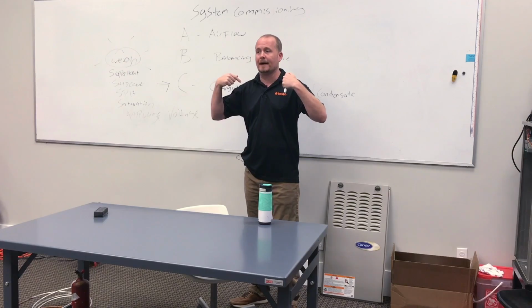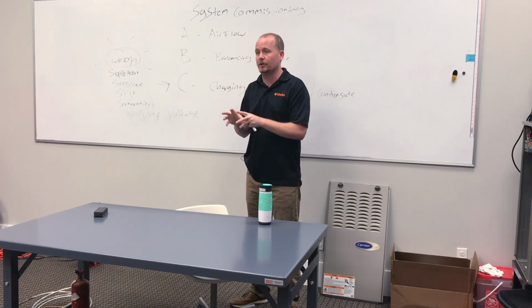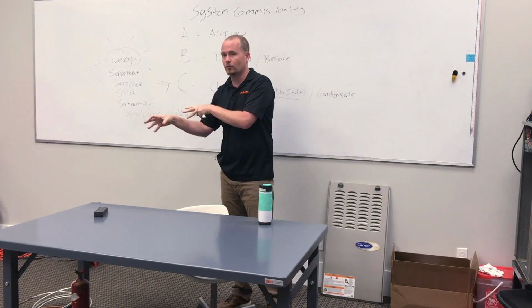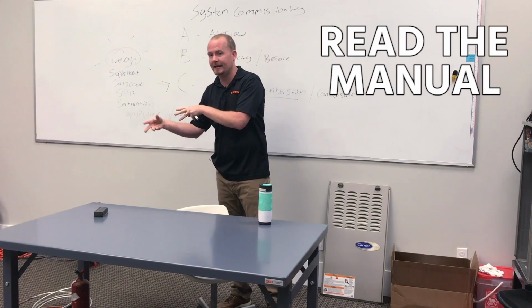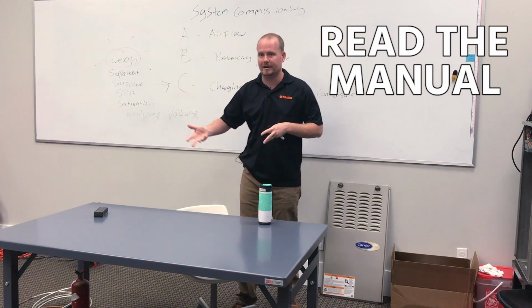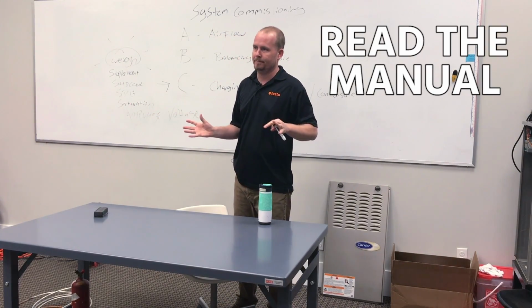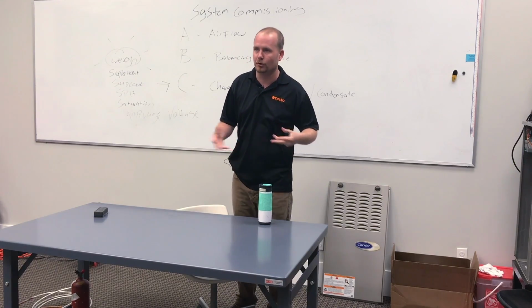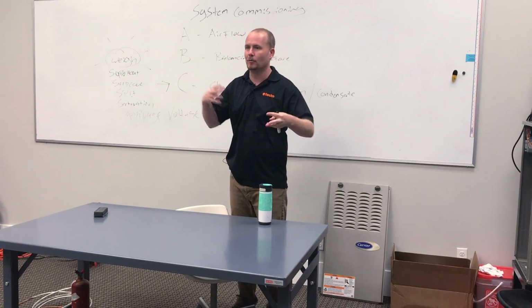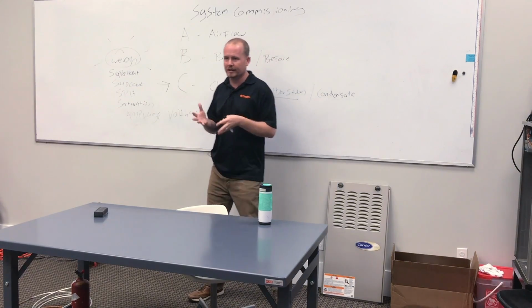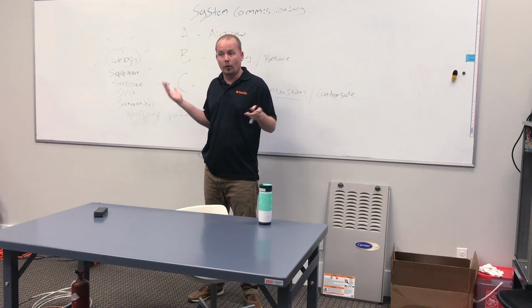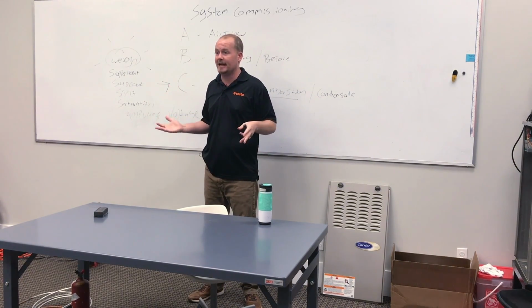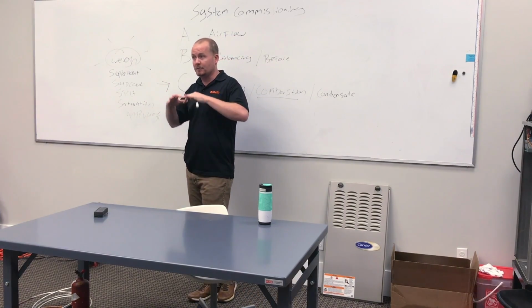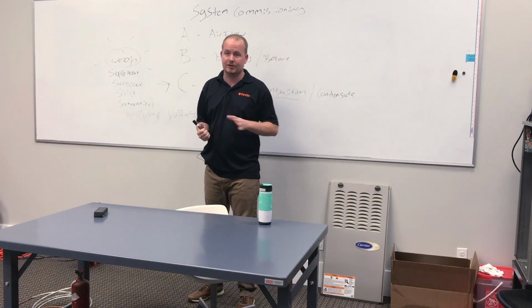Again, this is why we talk about, in order to know how to commission a particular piece of equipment appropriately, what do you need to do? Read the manual, right? You have to read the manual because not every piece of equipment is the same. You have a system that's got a belt-driven pulley, or greasable bearings, or there's all these things that you've got to look at on various pieces of equipment. So in order to know a piece of equipment, you've got to read the manual. Or you have to have worked on it enough to make enough mistakes to know everything there is to know. And with as many different types of equipment as we work on, that's not generally practical.